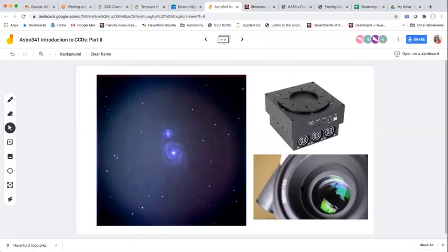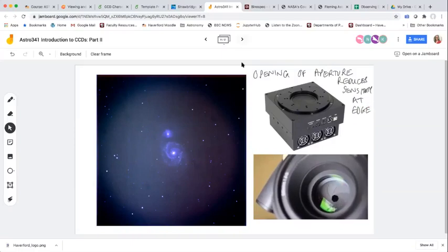So what's going on? I found a GIF showing what's going on. This is not our CCD, but this is a camera with a shutter that's opening and closing. You can just about make out the petals. So the way the aperture opens and closes is in this sort of method, and as you can imagine, that means that the center of it gets more time being illuminated by photons than the outer parts of it. And so we have this variation of sensitivity. So the opening of the aperture reduces the sensitivity at the edge of the chip, just from the optical path.